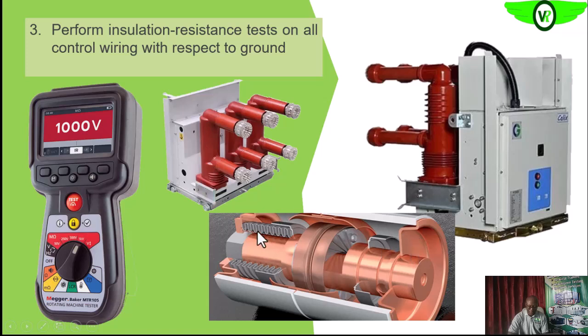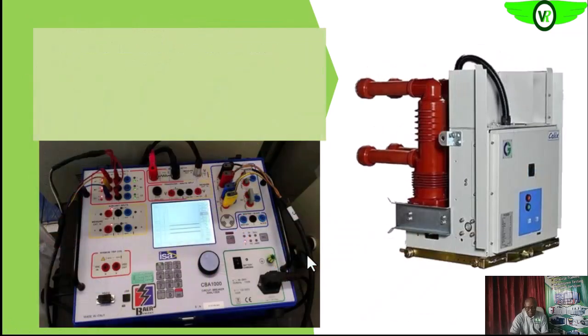This is the capsule housing the vacuum. This is the movable part of the contact, and this is the stationary part. When it is closed and you probe these two ends, what you are doing is testing the resistance between these contacts. So that is the contact pole resistance test.